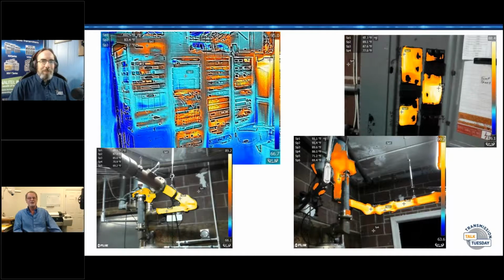Metal objects will reflect the ambient temperature around them. So like that bottom left image where you see a hot spot, it could be that's a hot spot, or it could just be shiny, reflecting heat from a transmitter close by. The angle of the image I'm taking there, it's just reflecting ambient heat.